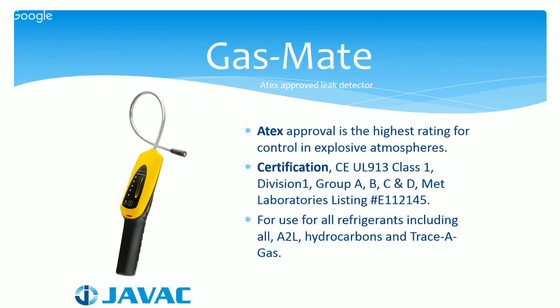As with all JAVAC leak detectors, they are highly sensitive to the refrigerants which the sensors are set to. And under F-gas regulations, the standard for leak detectors' detection rate should always be under 5 grams per year. The Gas-Mate will easily detect to the equivalent of 1 gram per year. So this detection rate makes the Gas-Mate very accurate when pinpointing the smallest of leaks on any R32 systems.